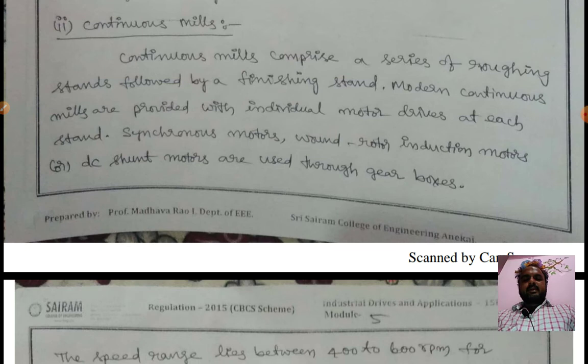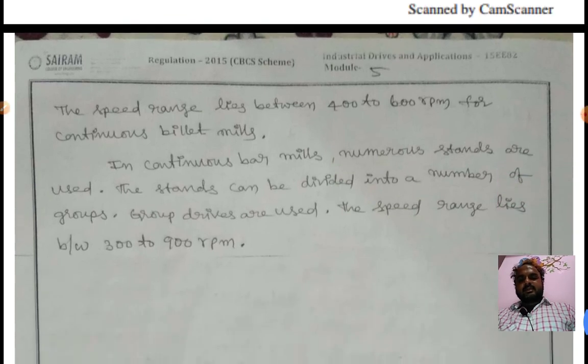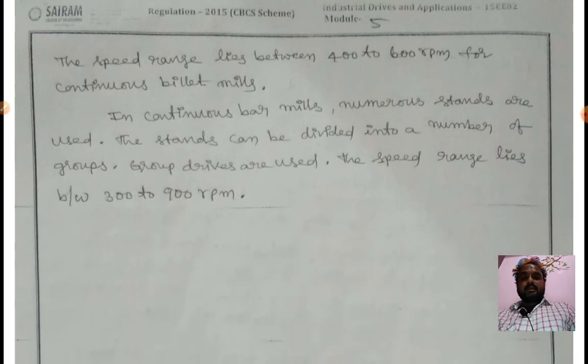Speed can be controlled by varying field excitation or resistance. The speed range lies between 400 to 600 RPM for continuous billet mills. In continuous bar mills, numerous stands are used that can be divided into groups. The speed range lies between 300 to 900 RPM.